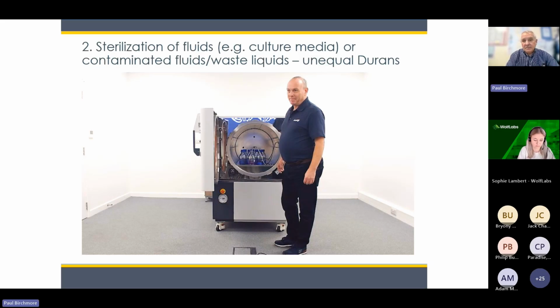Also, bear in mind, everyone uses Duran glassware, but if it was a type of load which was going to be used in a polypropylene bottle, then again, those things will change the characteristics of the heat up time. So glassware heats up at a very different speed to polypropylene. So you wouldn't want to mix and match the types of bottles or the types of glass and containers within the load as well. So keep it consistent. Same size bottles, same size volumes within the bottles, same bottles, and then you won't have any inconsistencies in your process.